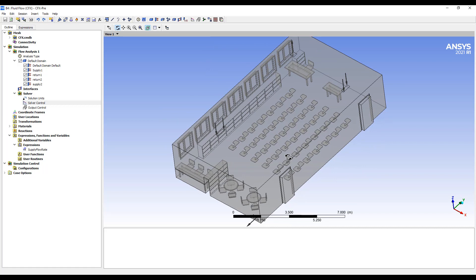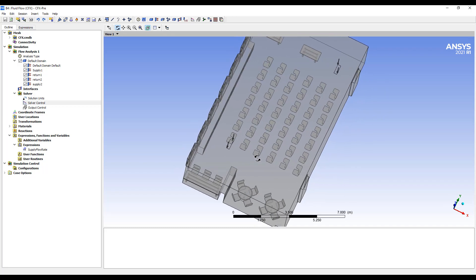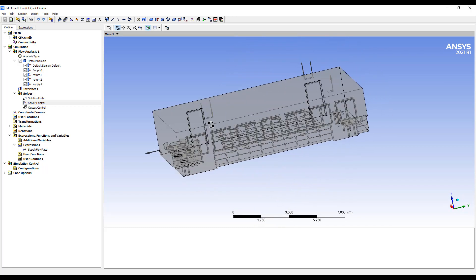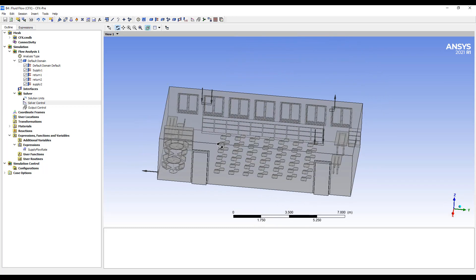We'd expect the classroom overall to have air that hasn't been around for all that much. So if you look at an ACH of 6, we would want, theoretically, this air to be totally replaced every 10 minutes.